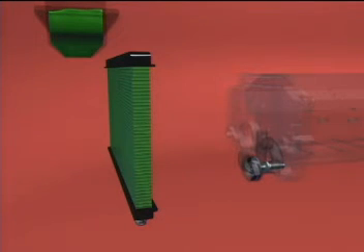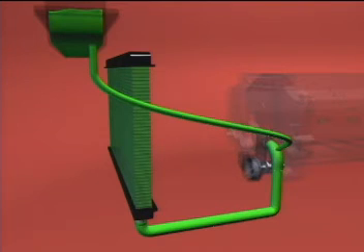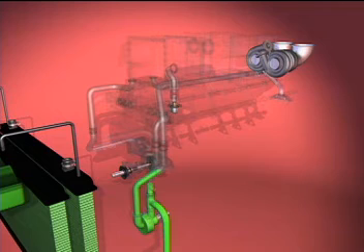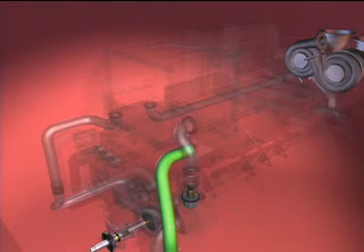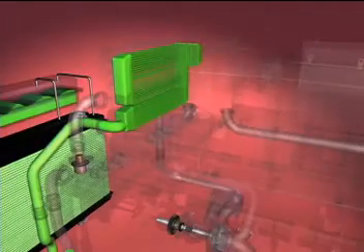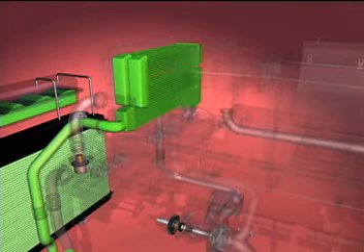In the LTA loop, coolant is drawn through the water inlet by the gear-driven LTA water pump mounted on the lower front left side of the gear cover. From the LTA water pump, the coolant travels through a supply tube to the lower connection on the left side of the aftercooler. In the aftercooler, the coolant circulates through the tubes in the second stage of the core to further reduce the temperature of the intake air from the turbochargers.